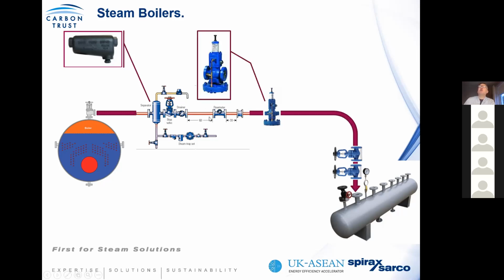You should then look at pressure reduction from the boiler to the distribution system. Why? The boiler is designed to generate steam at a certain pressure and should operate within its design parameters. However, you may not want the same design pressure within your distribution system, because the higher the distribution pressure, the higher the distribution losses. So you should then immediately step down your boiler pressure to your distribution pressure, such that you can minimize the distribution losses while still operating the boiler at its design condition.